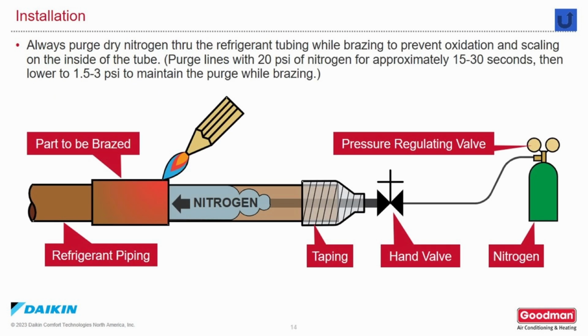Always purge dry nitrogen through the refrigerant tubing while brazing to prevent oxidation and scaling from building up on the inside of the tube. Purge lines with approximately 20 psi of nitrogen for about 15 to 30 seconds. Then lower the pressure to 1.5 to 3 psi and maintain a steady purge while brazing.